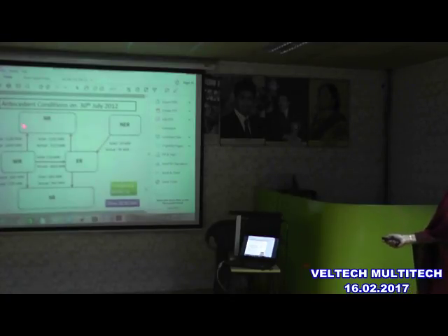This happened on the 30th July, resulting in a phenomenon called blackout. What really happened was, in the NR region, the power was supplied from the western region. Can you see here what the schedule is? Somebody can read the schedule for the western region? What is the actual? So actual was less, correct? So schedule was more. When the actual is going to be high, the problem starts. What is the schedule? Actual?